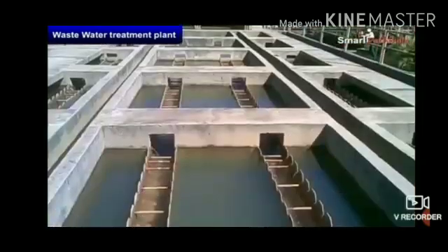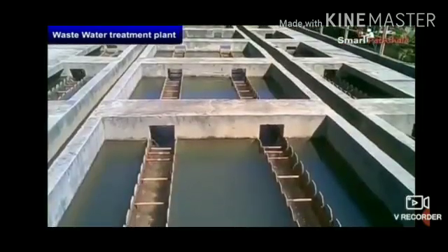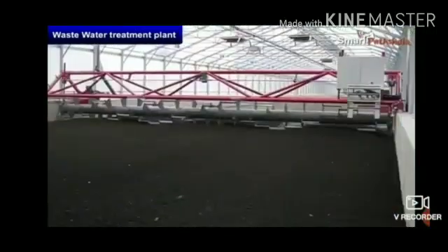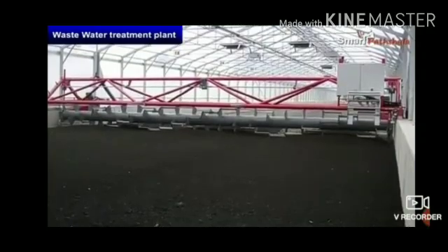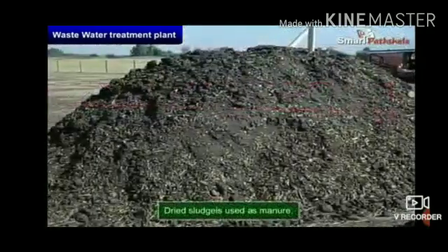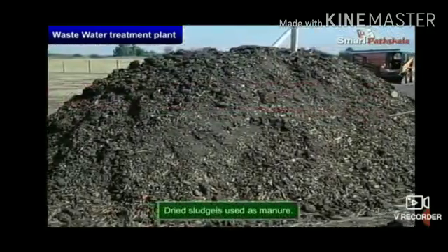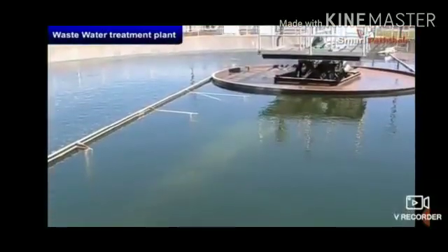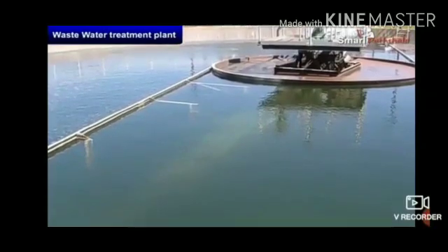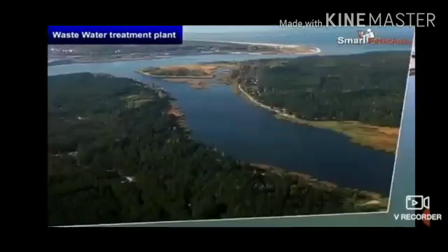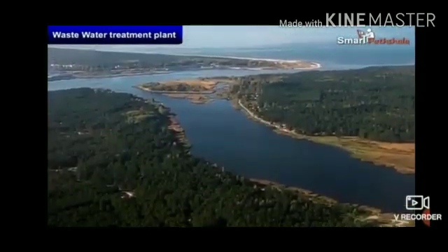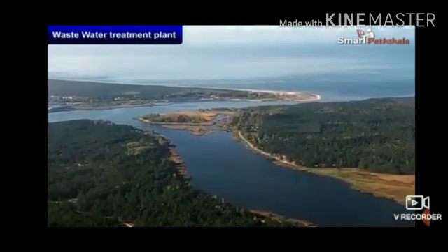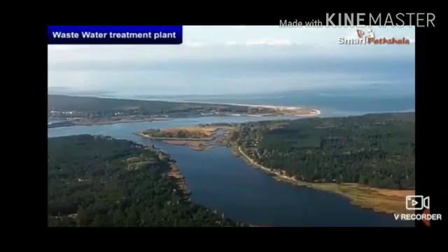The activated sludge is about 97% water. The water is removed by sand drying beds or machines. The dried sludge is used as manure which returns the organic matter and nutrients to the soil. The treated water has a very low level of organic material and suspended matter. It is discharged into a sea, a river or into the ground. Nature cleans it up further.